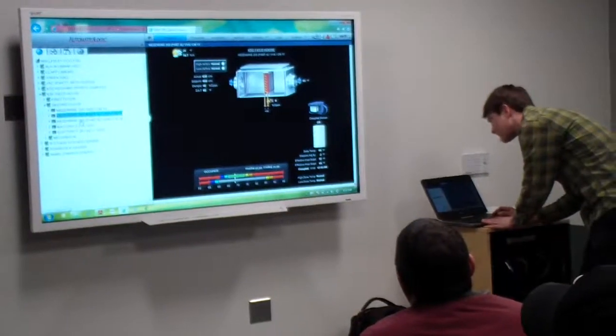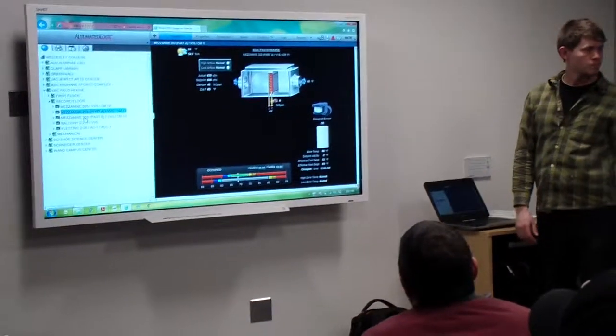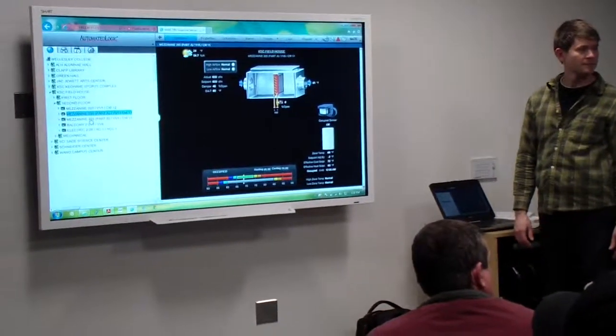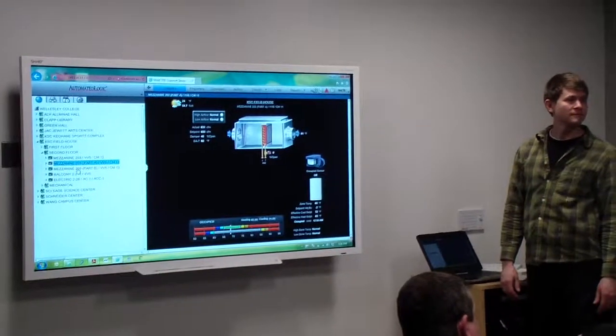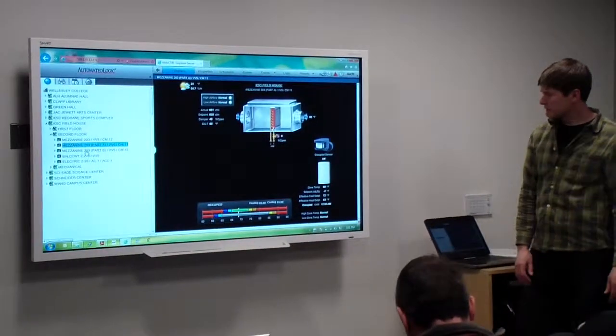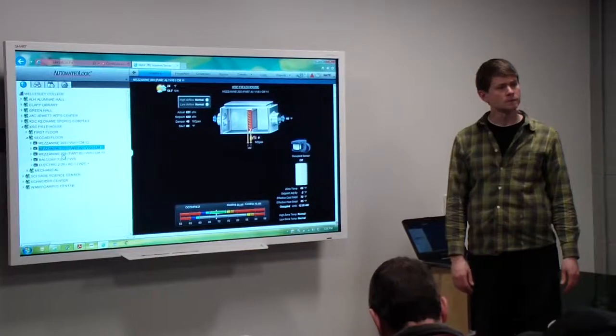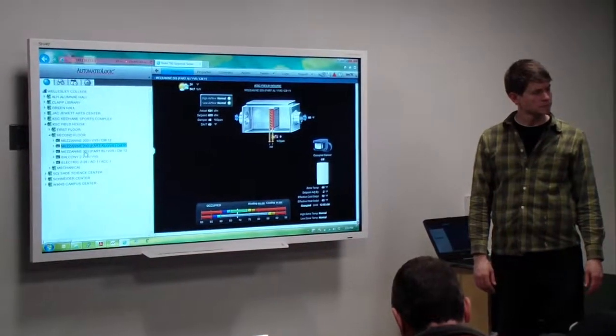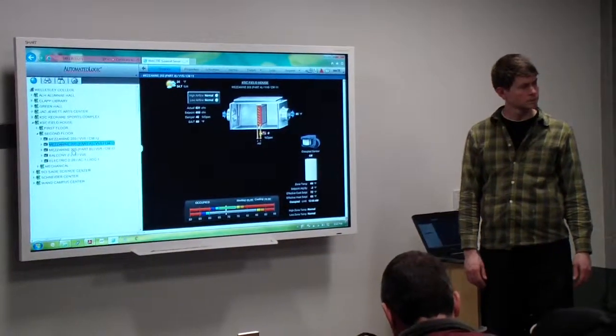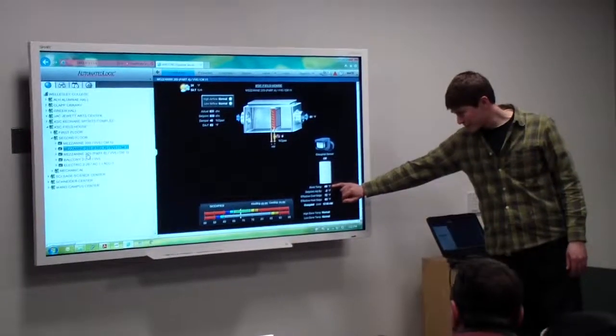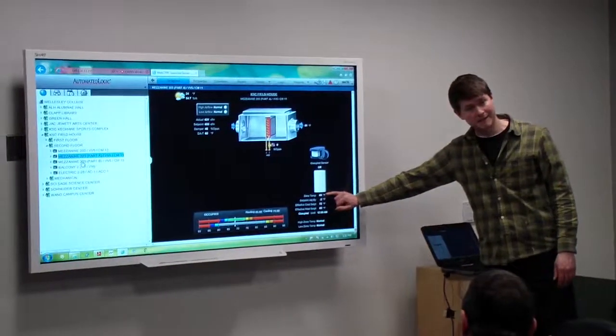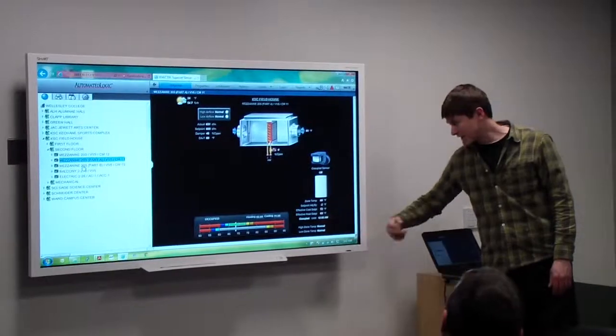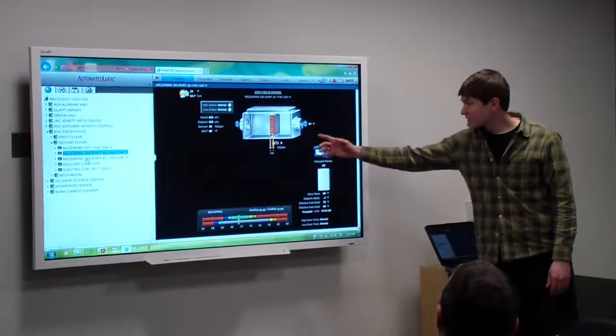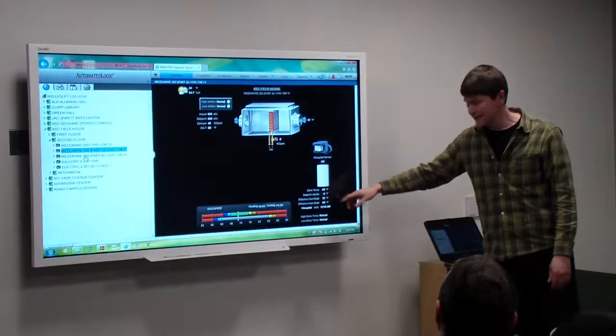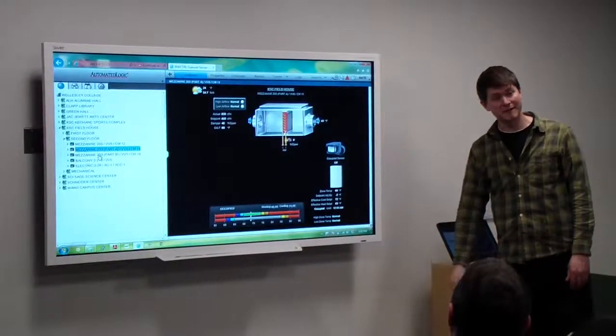Do we need to do that, or should they stay? You don't have to do anything if you don't want to. If you start getting complaints that they're too cold... Some of the complaints are still that it's too warm and not enough fresh air. But right now, when we drop the set point to 65, if you start getting complaints they're too cold, just grab the slider and bring it up, because we're dropping it down a little bit. These rooms are still sitting at 69 at the moment. With a 61 degree output, it's going to take a little bit for it to bring that down.